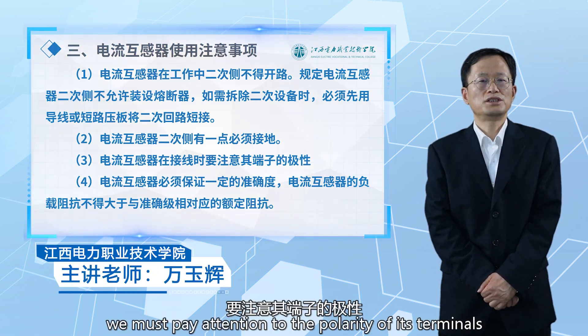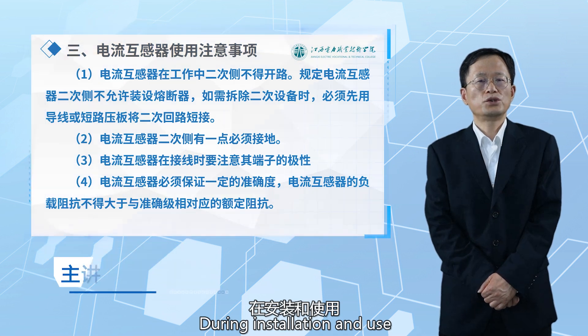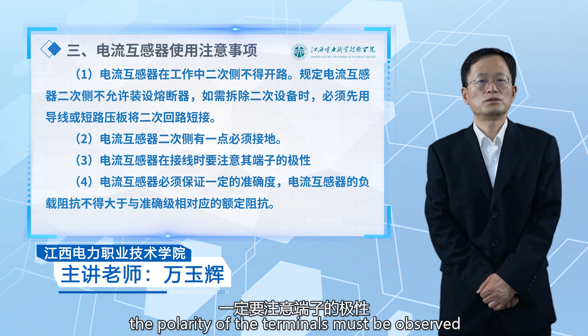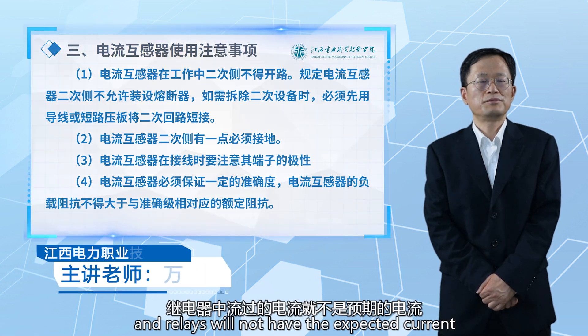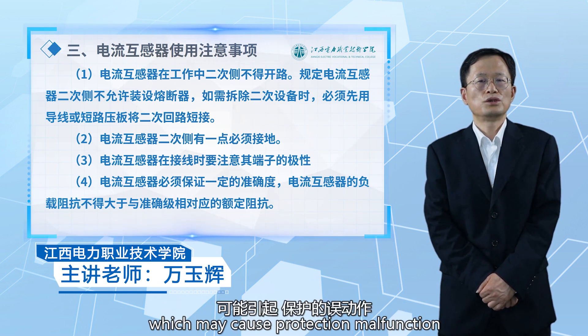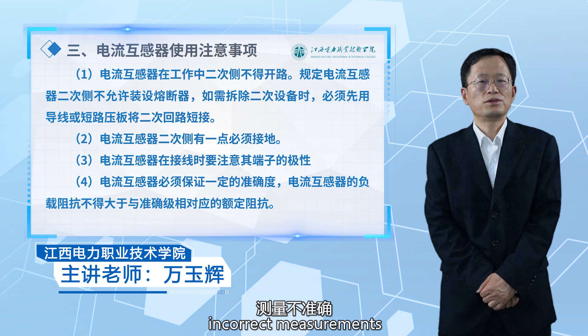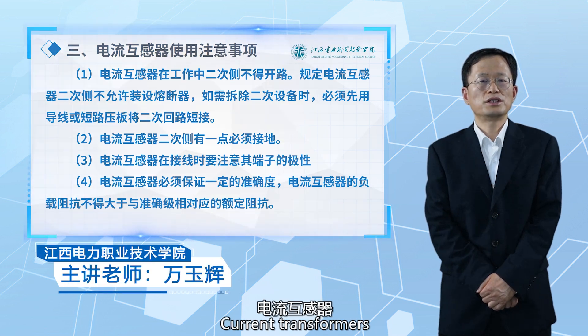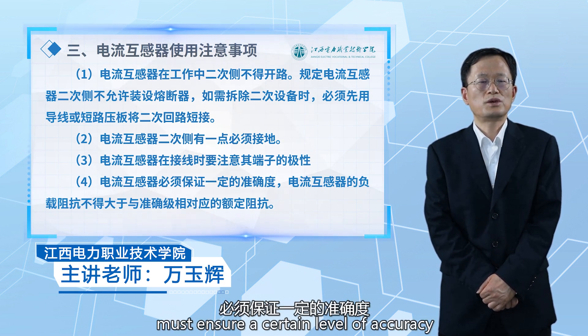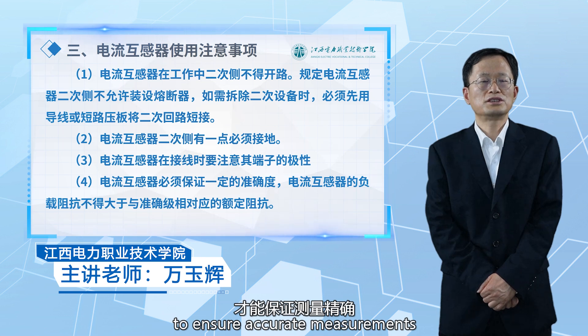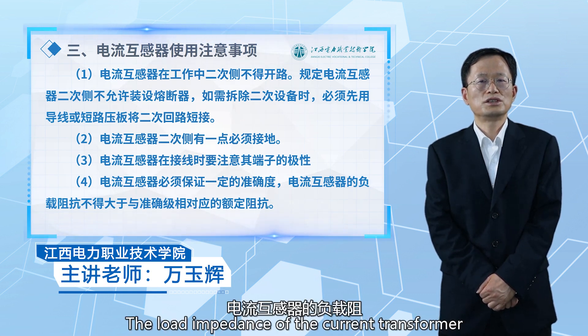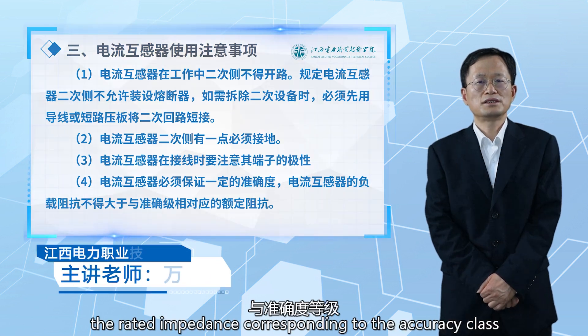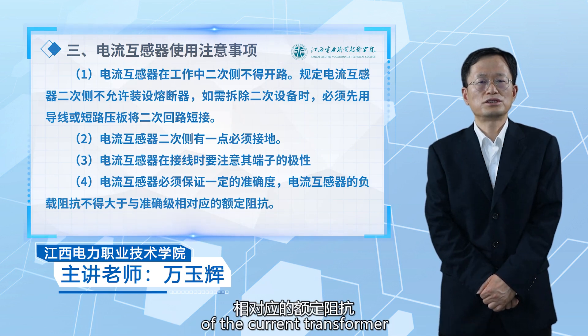During wiring of current transformers, attention must be paid to the polarity of the terminals. If polarity is not observed, the secondary instruments and relays will not receive the expected current, which may cause protection malfunction, incorrect measurement, or damage to the instrument. Current transformers must also ensure a certain level of accuracy for accurate measurement and proper operation of protection devices. The load impedance must not exceed the rated impedance corresponding to the accuracy class of the transformer.